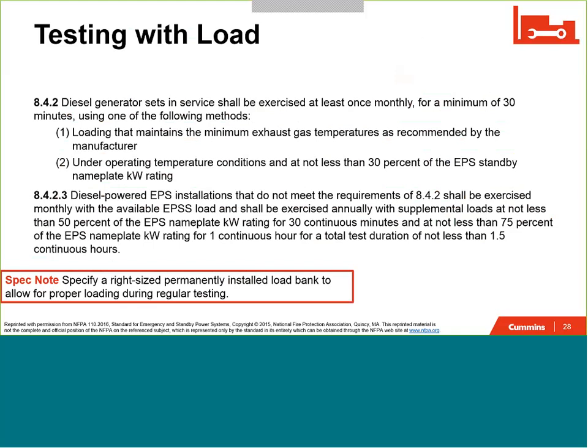Some comments here about testing with load, another question that we get quite often, especially about diesel generator sets. NFPA 110 very clearly calls out how you should be testing a product on a regular basis. It says it shall be exercised at least monthly, that's once a month, for a minimum of 30 minutes using one of the following methods. And there are two methods recommended here. The first and foremost, and typically the most preferred by engine and generator manufacturers, is to load the generator set until the engine exhaust temperature meets a level as recommended by the manufacturer. Now, as you can imagine, you have to do a little bit more work to accomplish this.